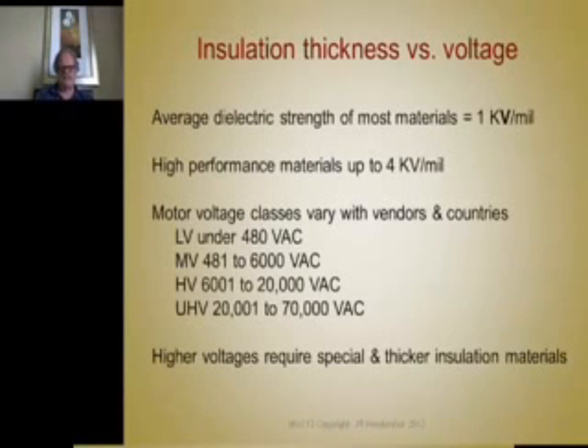The average dielectric strength of most insulation materials is at least 1,000 volts per mil, and many of them are as high as 4,000 volts per mil. The motor voltage classes vary with vendors and countries, but low voltage is considered under 480 volts AC. Medium voltage is 481 to 6,000 volts AC. High voltage is 6,001 to 20,000, and ultra high voltage is 20,000 to 70,000.